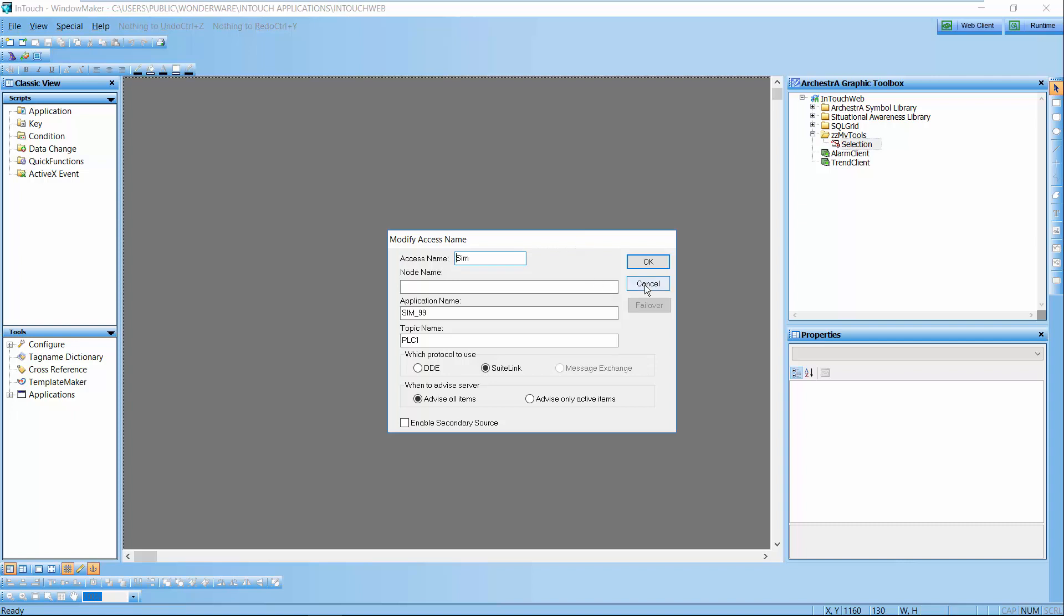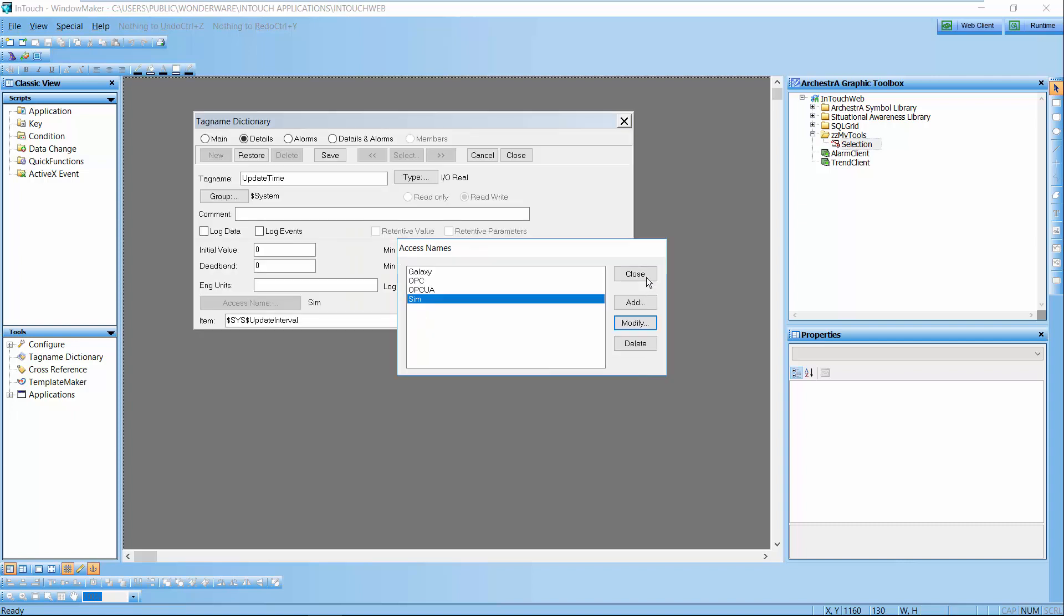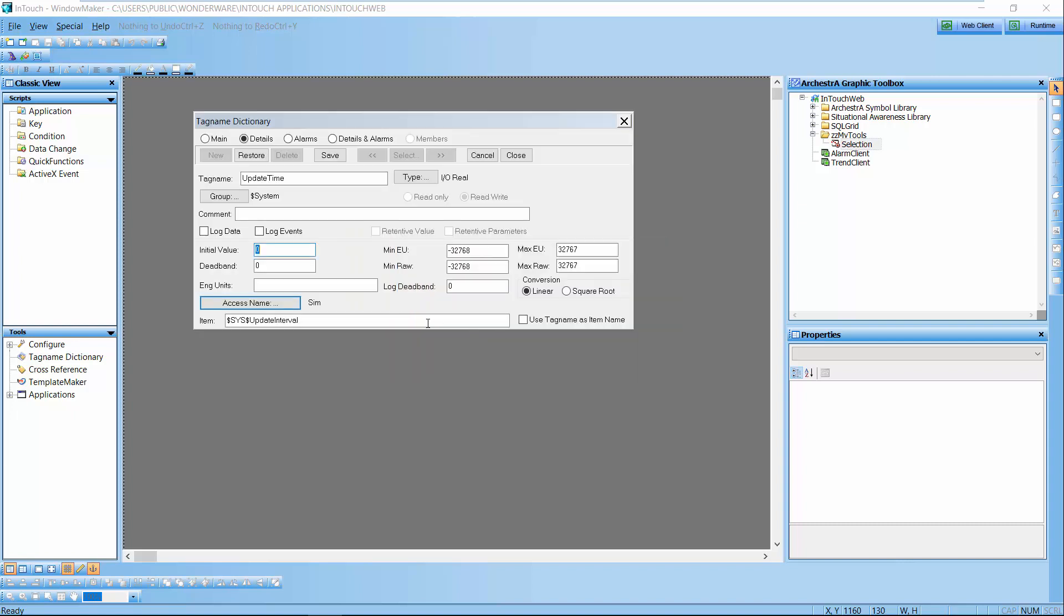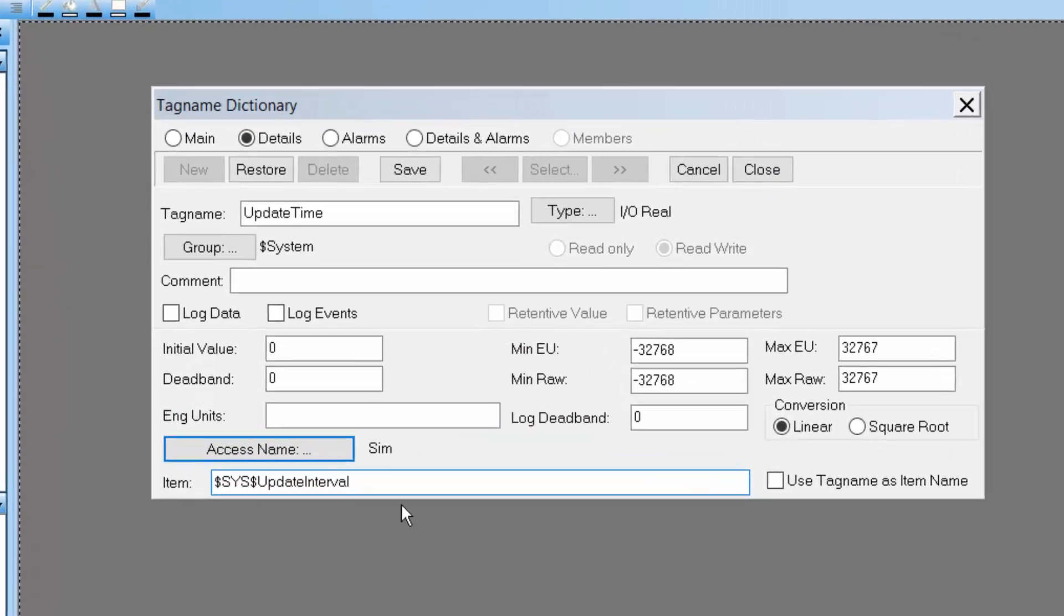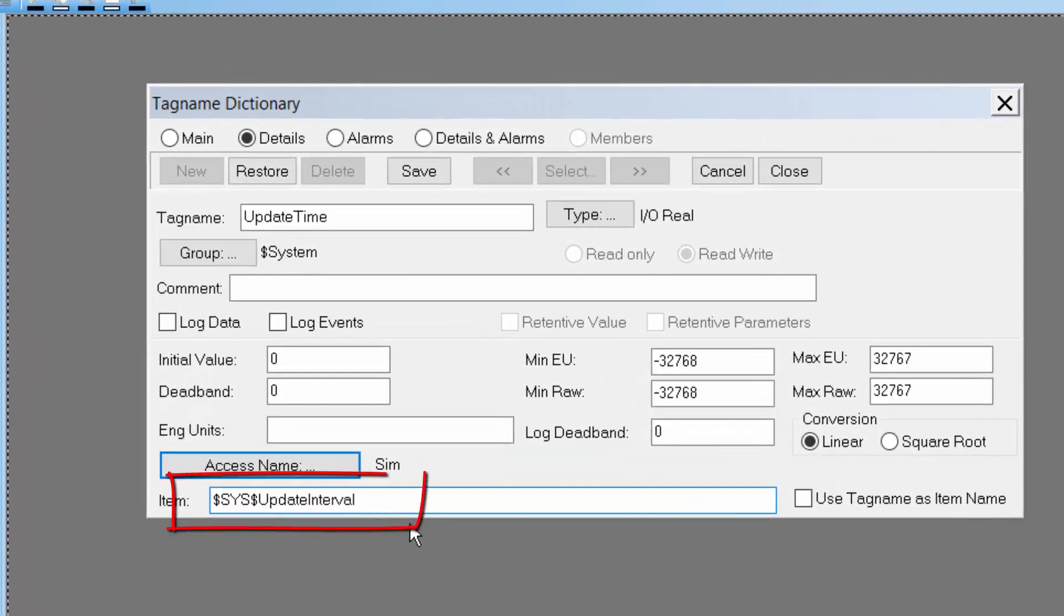But the actual variable that I'm changing is the sys$updateInterval. It's built into all the Wonderware drivers so this is the variable I'm writing to when I'm changing the screen to change the different poll rate.